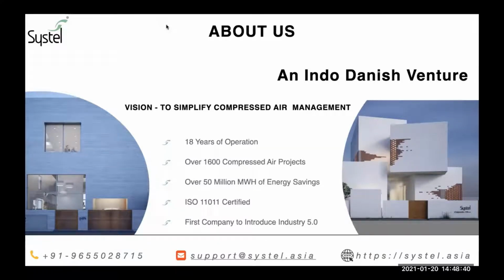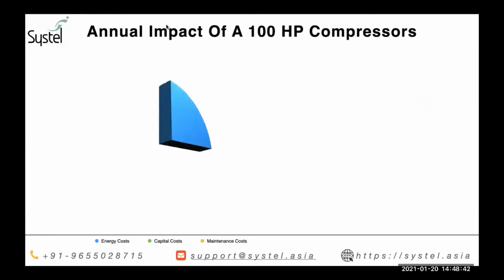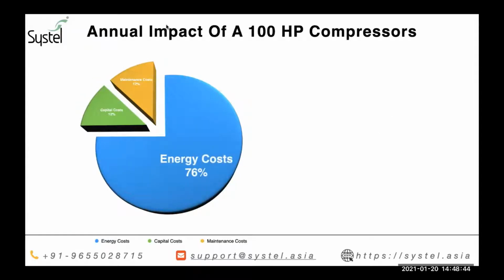We might be aware that energy is the major chunk of the life cycle cost of a compressor. But what largely is overlooked is the sustainability side of it. Here I would present that a 100 HP compressor in a year consumes close to 648,000 kilowatt hours, and converting it at 7.5 rupees per kilowatt hour, it is close to 4.8 million rupees. That is the energy cost incurred for running a 100 HP compressor.